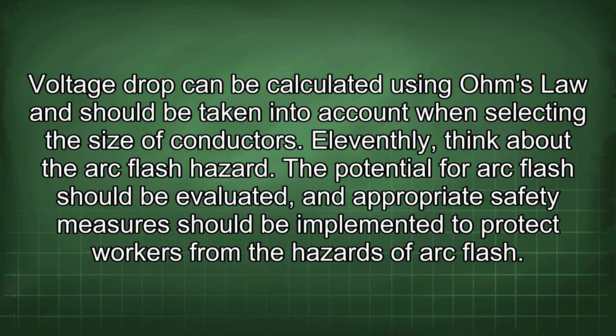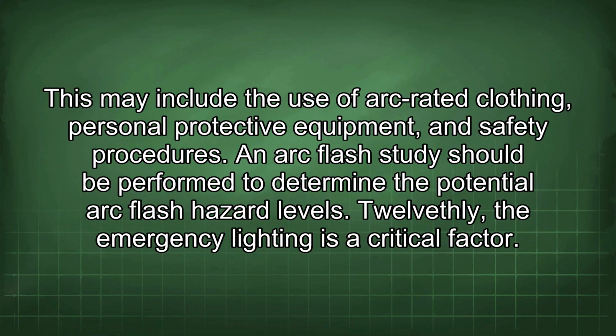11thly, think about the arc flash hazard. The potential for arc flash should be evaluated, and appropriate safety measures should be implemented to protect workers from the hazards of arc flash. This may include the use of arc-rated clothing, personal protective equipment, and safety procedures. An arc flash study should be performed to determine the potential arc flash hazard levels.